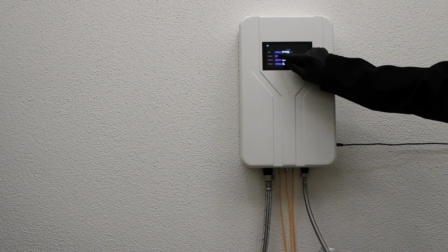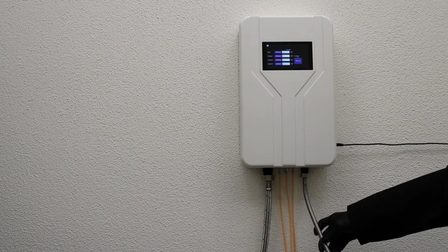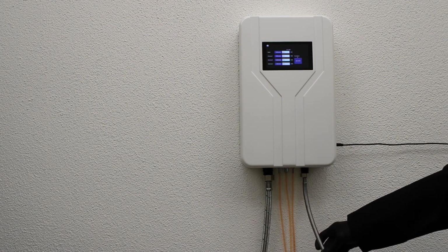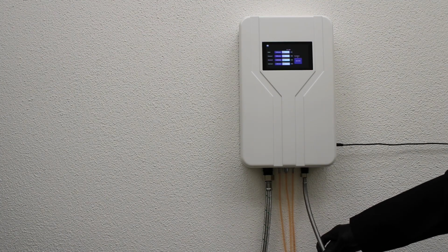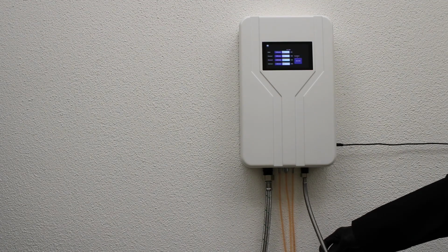Hold the output hose of the dosing system firmly in the container, as the system will run the chemical into the container for 30 seconds once you initiate the calibration. Please note that the calibration process cannot be interrupted. When you are ready, press the Calibrate field next to Chemical 1 in the Calibration section. The dosing system will now dispense the chemical into the container for 30 seconds and then stop automatically.